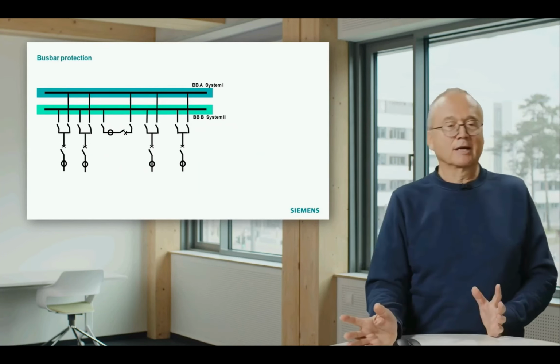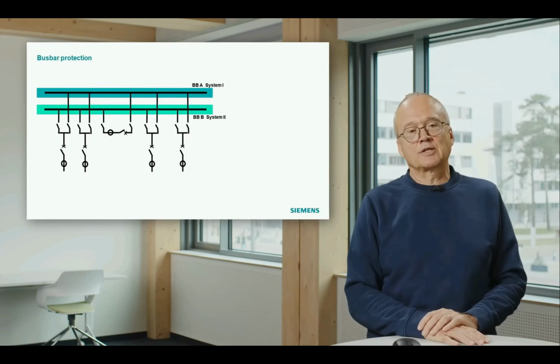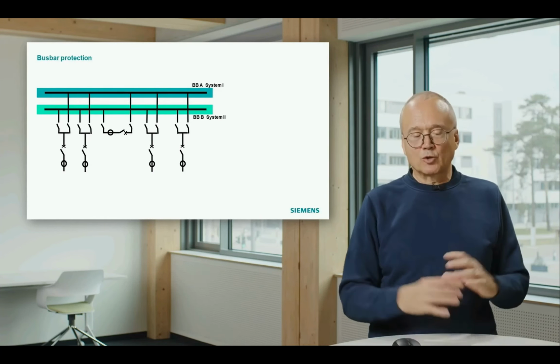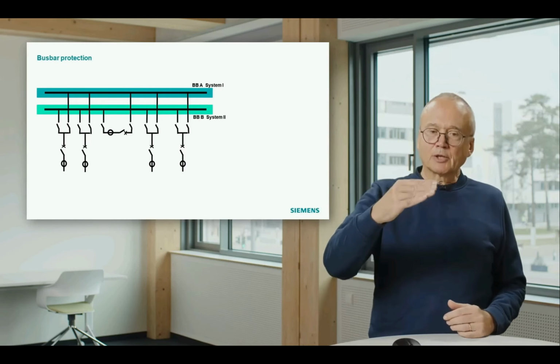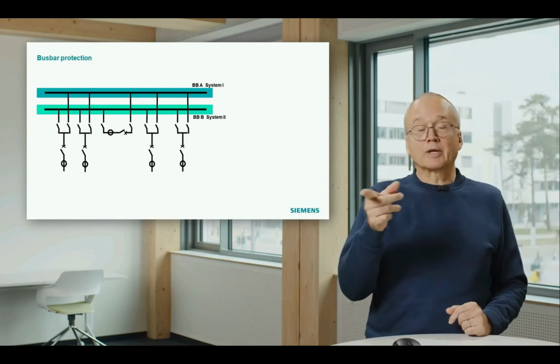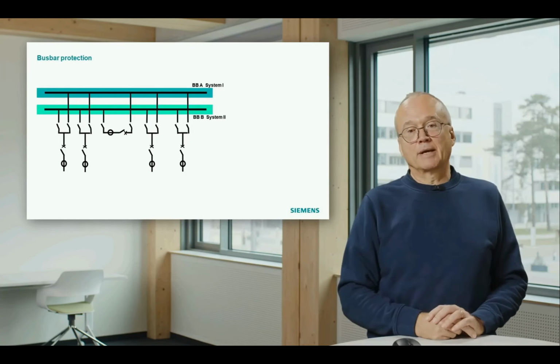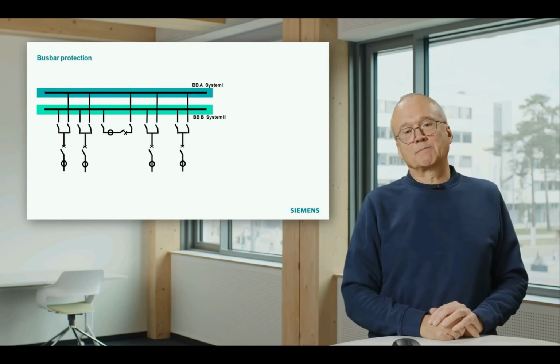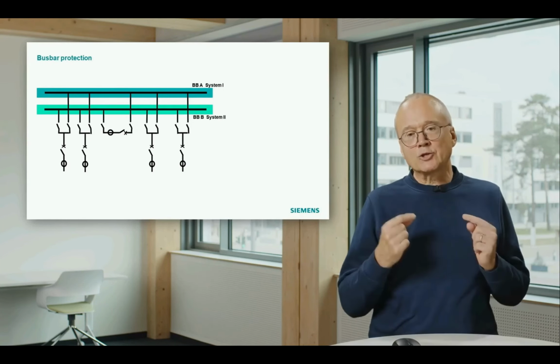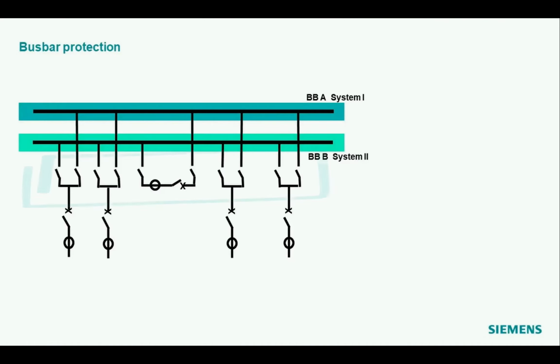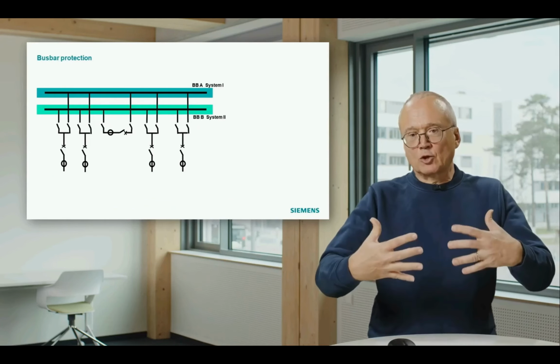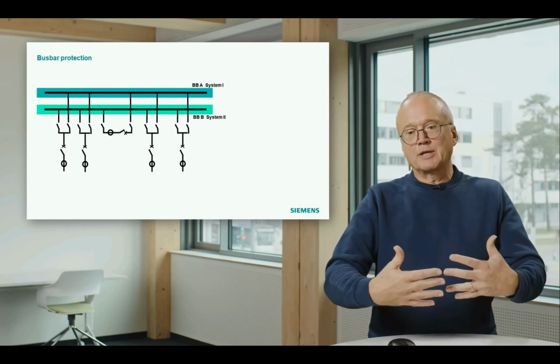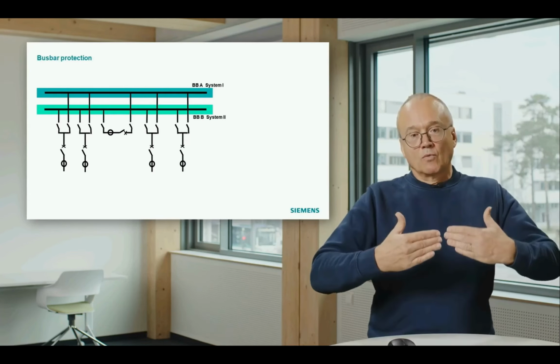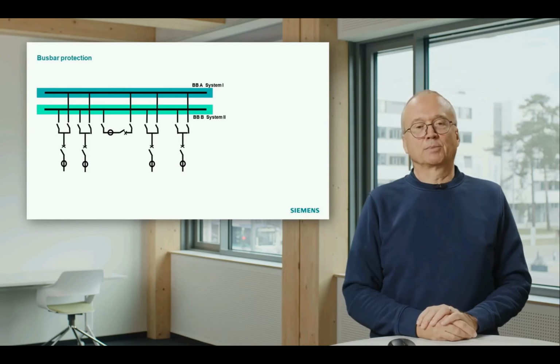Or even both isolators are closed in special situations. And of course, we want to apply the differential principle separately for both busbars. That means we want to calculate the differential current for busbar A and the differential current for busbar B separately. And to do that in a proper way, we must take into account the position of all these disconnectors here. That means we must combine the topology information, position of disconnector, with the measurement to apply the principle.